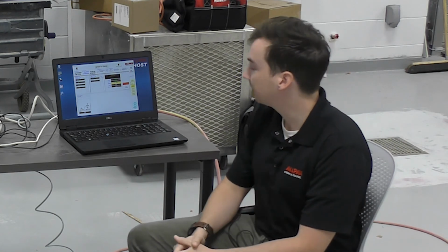Correct. And instead of pausing, let's say you reach your temperature faster than you expected, could you skip ahead? Yes, that's what you would use the system overrides menu for. If I wanted to extend the cook, say my come-up time was a little shorter than what my validated process says it should be, and I wanted to increase my cook time by about 30 seconds, I have to push the pause and leave it pressed for 30 seconds past the normal end of the cook cycle.